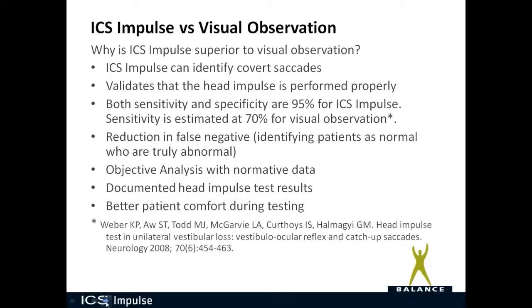ICS Impulse provides objective analysis with normative data and documented head impulse test results, rather than just a handwritten note as with visual observation. It also provides better patient comfort during testing. When doing visual observation, you have to do quite large head impulses — neurologists currently using visual observation are often performing head impulses over 300 degrees per second. With ICS Impulse, you don't need that big a head movement; in fact, that big a movement causes artifacts. Keep your head impulses in the 150 to 200 degrees per second range, and patient comfort is increased.